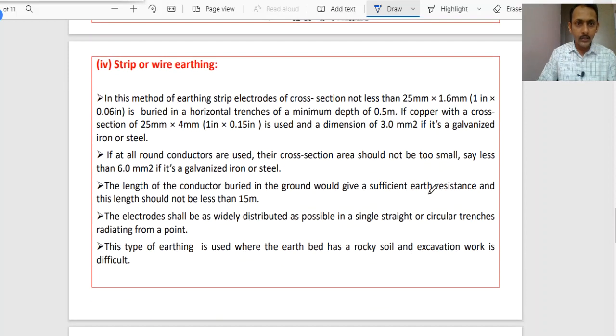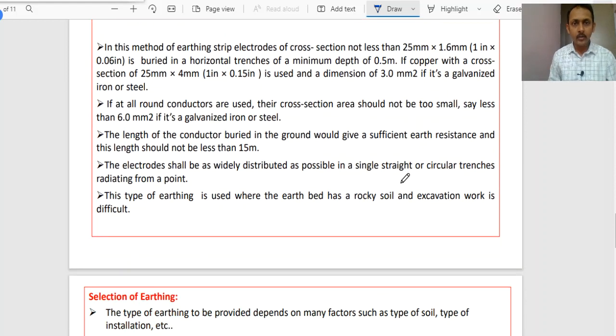Next one is the strip or wire earthing. In this method of earthing, strip electrodes of cross-section not less than 25 mm by 1.6 mm are buried in horizontal trenches of minimum depth of 0.5 meters, right? If copper is used, a cross section of 25 mm by 4 mm is used, and a dimension of 3 mm square if it is galvanized iron or steel, depending upon whether you are using copper or galvanized iron. The specifications are given, right? And they will be buried at a minimum depth of 0.5 meters, right?